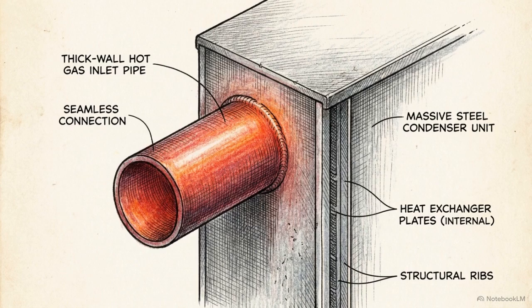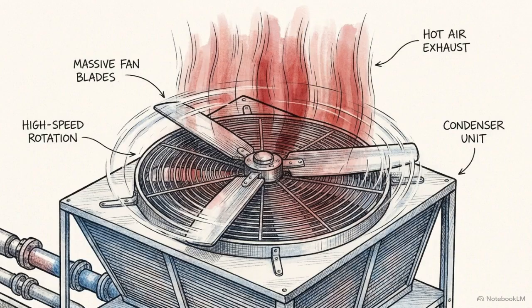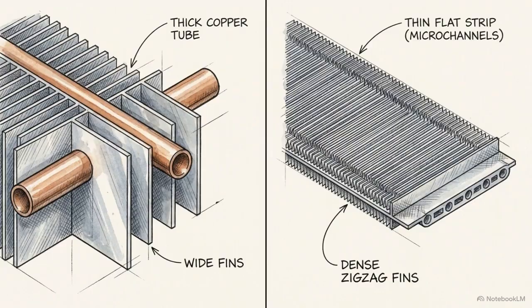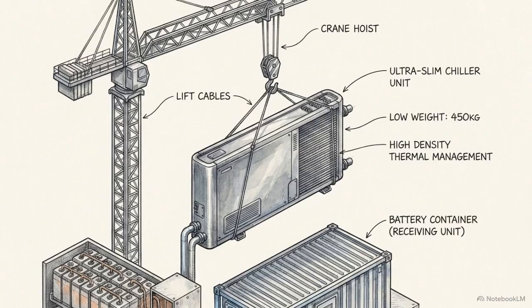The superheated, high-pressure gas then flows into the condenser. Massive fans pull ambient air across the condenser coils, rapidly drawing the heat out of the gas and ejecting it into the atmosphere. Modern BESS chillers have largely abandoned traditional fin tube designs in favor of microchannel condensers. Their flat, high-density geometry significantly reduces the overall weight of the unit and requires far less chemical refrigerant to operate effectively.